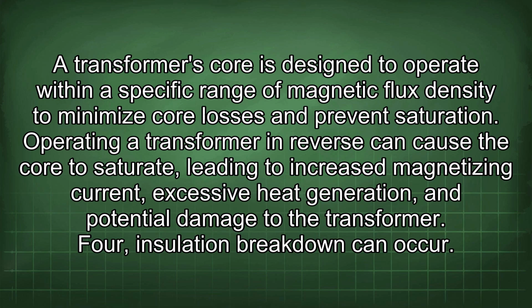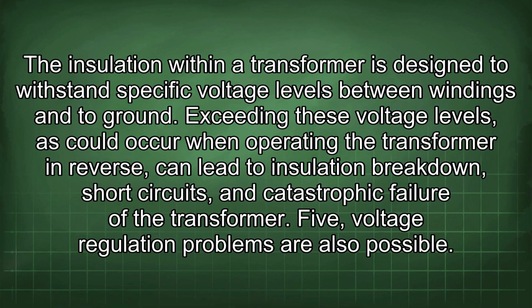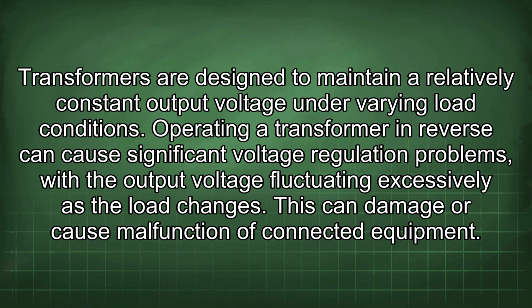Fourthly, insulation breakdown can occur. The insulation within a transformer is designed to withstand specific voltage levels between windings and to ground. Exceeding these voltage levels, as could occur when operating the transformer in reverse, can lead to insulation breakdown, short circuits, and catastrophic failure of the transformer. Fifthly, voltage regulation problems are also possible. Transformers are designed to maintain a relatively constant output voltage under varying load conditions. Operating a transformer in reverse can cause significant voltage regulation problems, with the output voltage fluctuating excessively as the load changes.